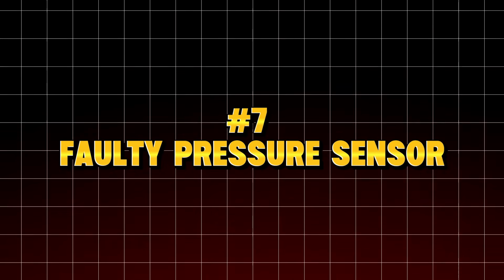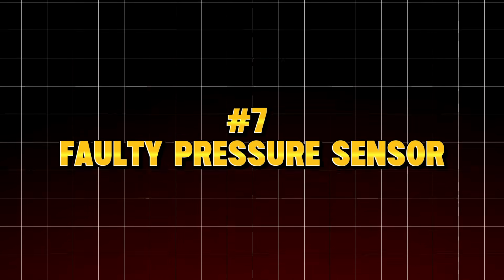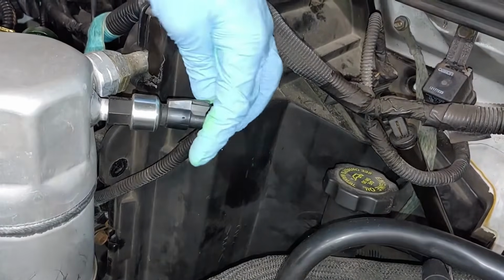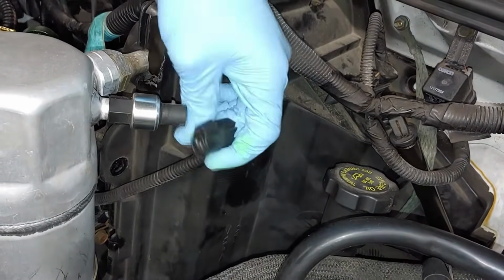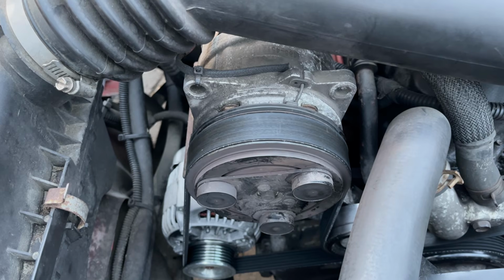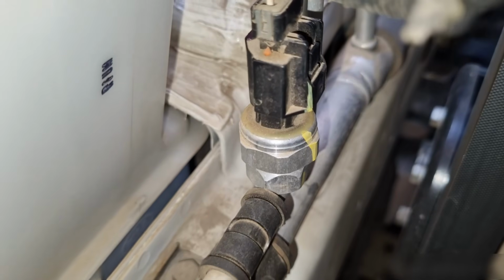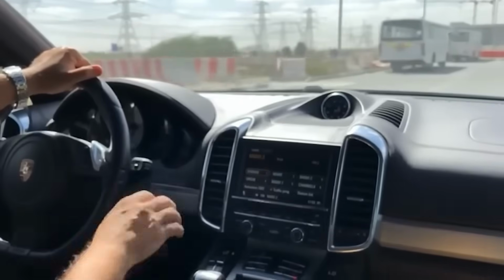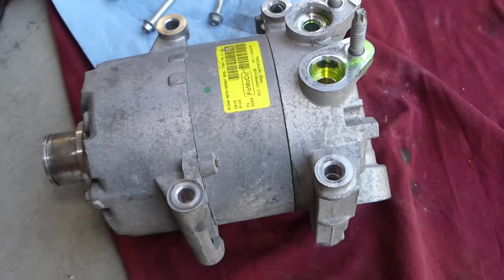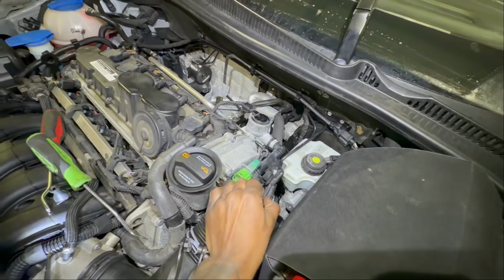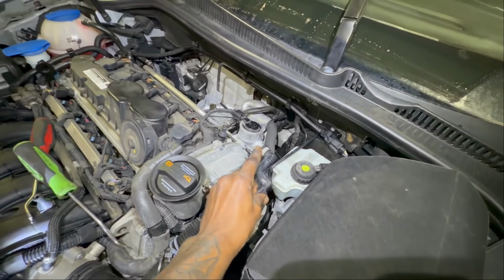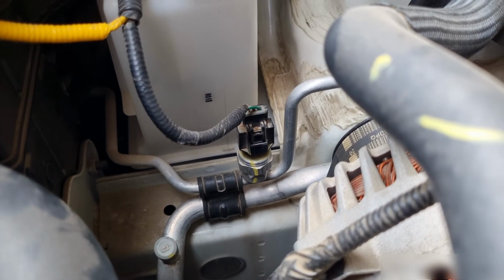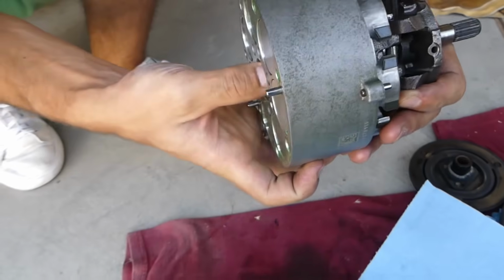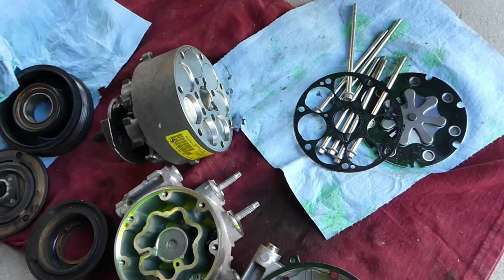Number 7. Faulty pressure sensor. Sometimes the refrigerant charge is correct, yet the compressor refuses to stay engaged. That's when I begin checking pressure sensors. Modern AC systems rely on these sensors to protect the compressor. If they send incorrect pressure information, the control module may shut the compressor off even though nothing is mechanically wrong. I've seen owners replace compressors when the only failed component was a pressure sensor.